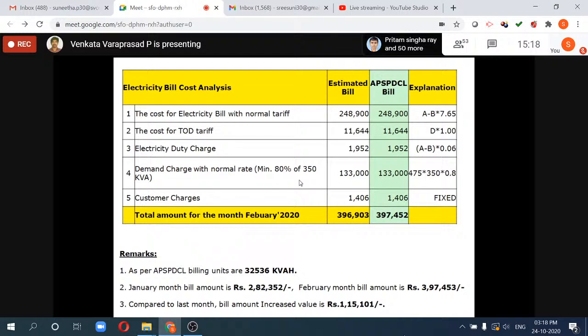So if your recorded maximum demand is only 80, they will still charge for 280. If it crosses 280, then they will charge based on whatever demand value is there. If it is 290, that means 290 into 475. If it is 349, that means 349 into 475.